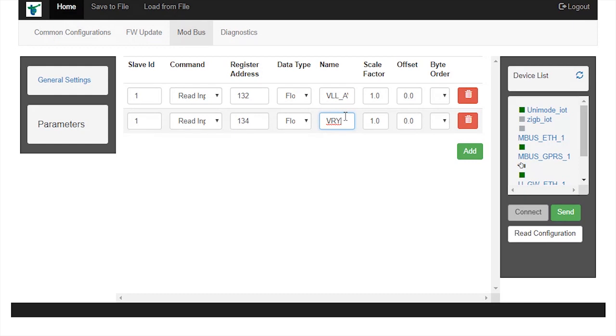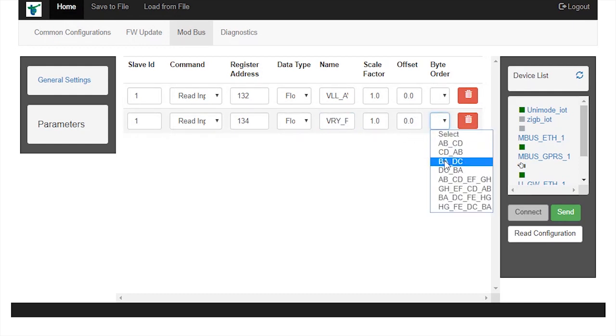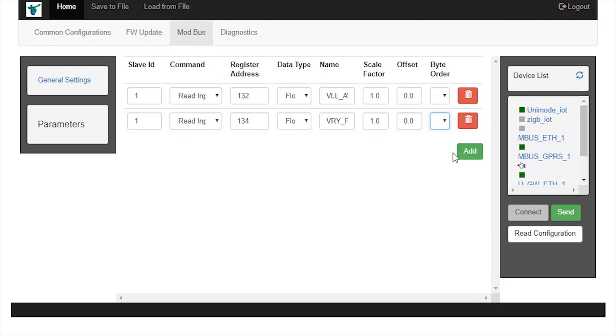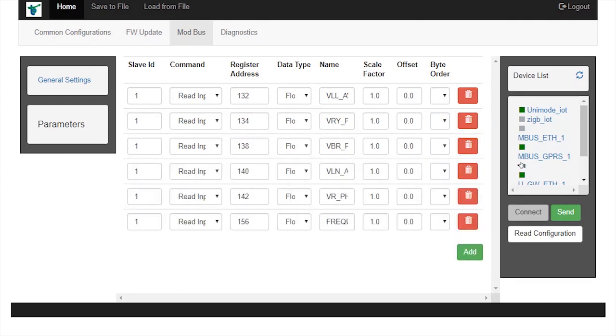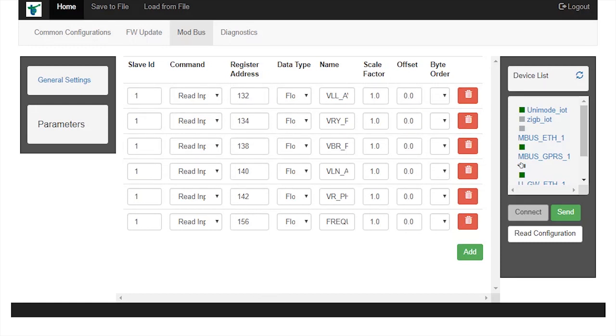Name as vry_phase, scale factor 1.0, offset 0, and byte order as cd_ab. I would like to read a total of 6 parameters of the digital energy meter, so I added 6 parameters.